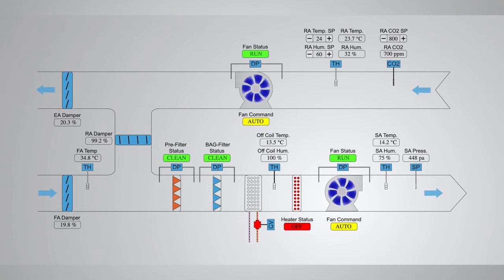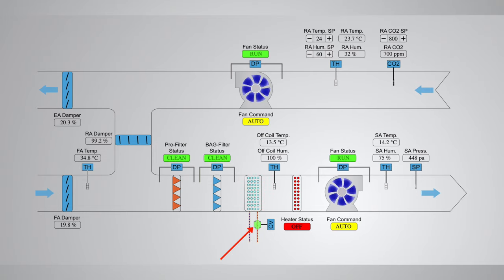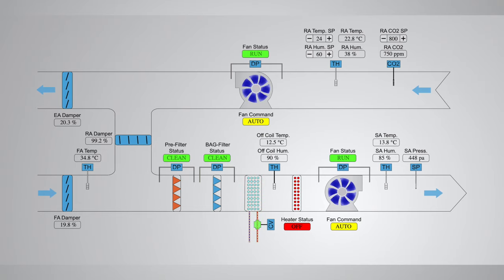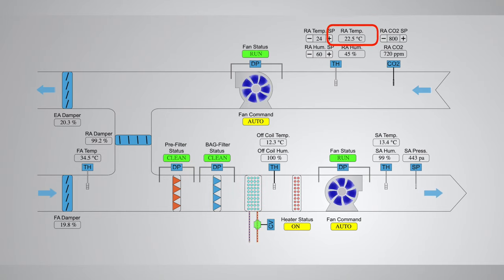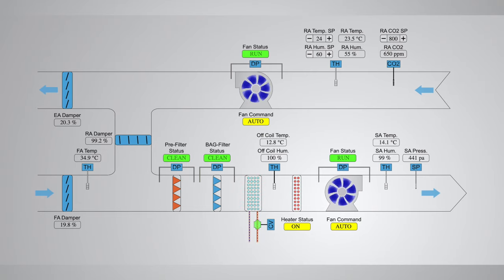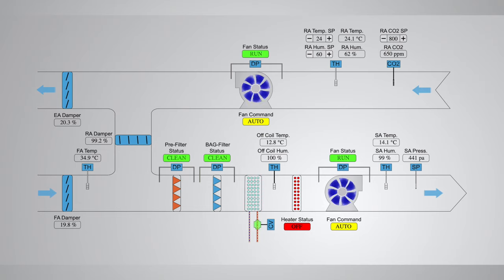Next is the humidity control loop. In this control loop, the return air humidity sensor is used to control the space humidity level. Humidity control is achieved by opening the chilled water control valve using a PID controller until the humidity set point is achieved. If the return air humidity falls below 60%, the control valve will be modulated to allow more chilled water to achieve the required humidity level. During this process, the return air temperature will go lower than the set point, so the electric heater will be switched on to maintain the temperature set point. It is important to note that since the control variable for both the temperature and humidity control loops is the chilled water control valve, the temperature control loop shall always be given higher priority. Once the temperature set point is achieved, the BMS will enable the humidity control loop based on the humidity set point.